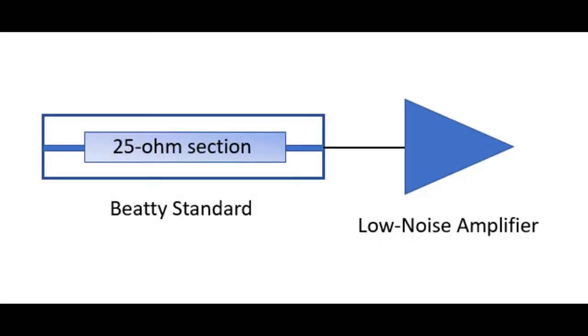Now for this experiment I chose to show an amplifier that I measured as part of an experiment where we're looking at de-embedding and its effect on noise parameters. So I measured the low noise amplifier by itself and then I also did a measurement of the low noise amplifier plus a Beatty standard. And a Beatty standard gives us a very well-known reflection coefficient that we can estimate what would happen to the noise figure if we put the Beatty standard on a well-known amplifier.